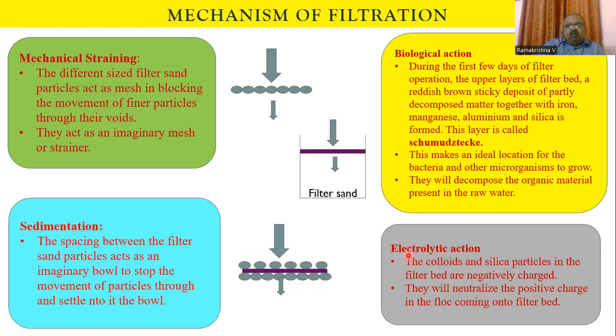Another mechanism is electrolytic action. Colloidal and silica particles present in the filter sand carry negative charges. The water contains chemicals with positive and other charges. As water passes through the filter bed, the positive charges of these impurities get attached to the negatively charged colloidal and silica particles — that is electrolytic action.